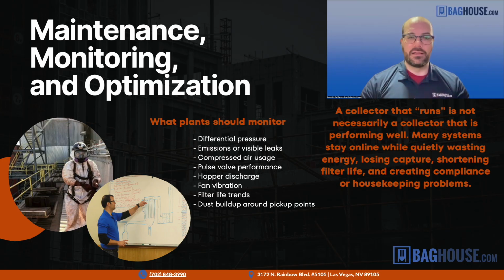And then finally, a lot of things that cause poor performance in the dust collectors can be traced back to shortcomings in the maintenance plan. So using the wrong kind of filters, letting them run too long, not taking care of these basic regular maintenance tasks. But some of it comes back to design flaws.